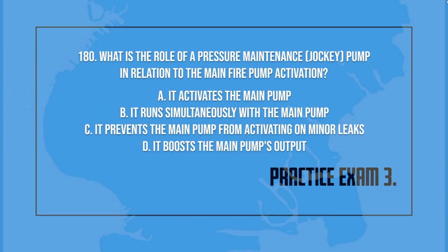(180) What is the role of a pressure maintenance or jockey pump in relation to the main fire pump activation? A. It activates the main pump. B. It runs simultaneously with the main pump. C. It prevents the main pump from activating on minor leaks. D. It boosts the main pump's output.